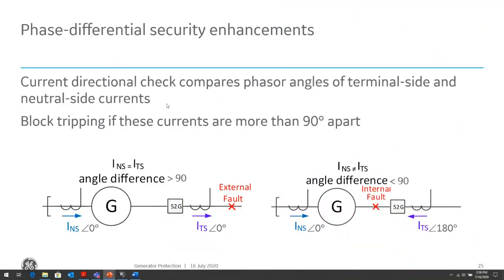The other principle that we have applied is a directional principle. Obviously, again, current in should be current out vectorially. So faults coming into the generator and leaving, for external faults, coming in and leaving. The angular difference between those for external faults should be greater than 90 degrees, or technically it should be 180 degrees. When there's an internal fault, there will be less than 90 degrees, or they're basically within 0 degrees of each other. Now, you'll notice that's kind of contradictory to what I said, with the angles that I'm showing at the bottom, where for an external fault, I'm showing 0 and 0, and for an internal fault, I'm showing 0 and 180.